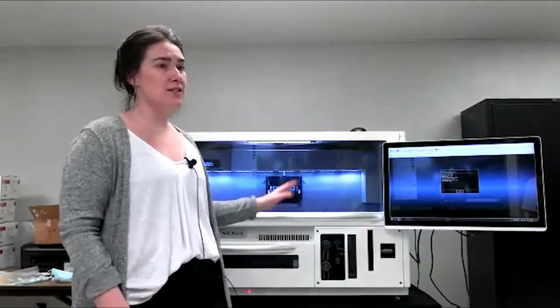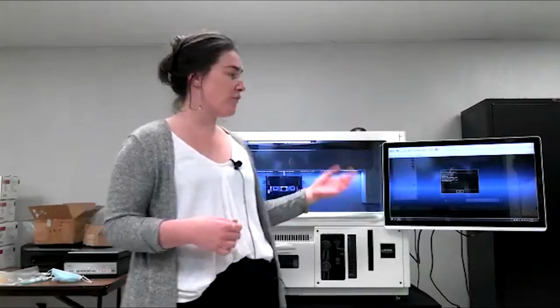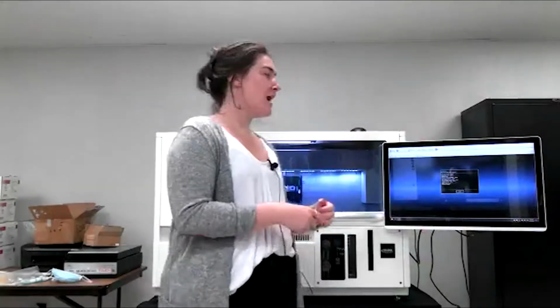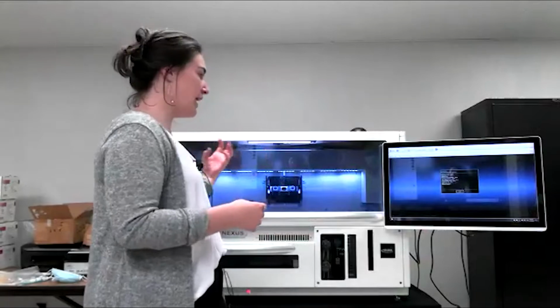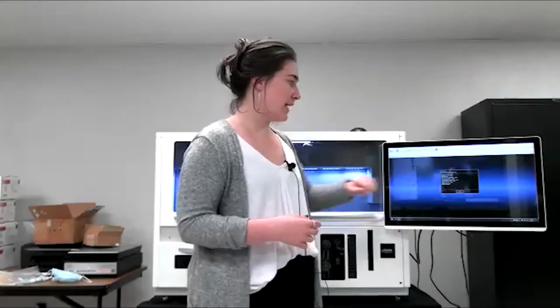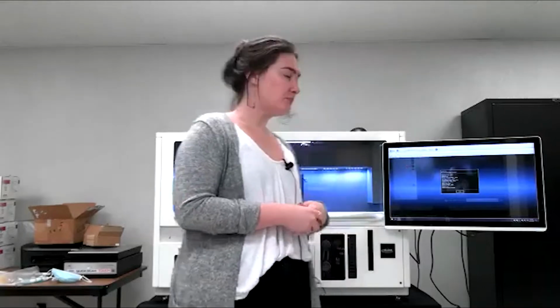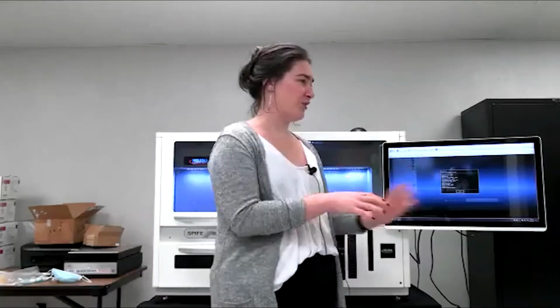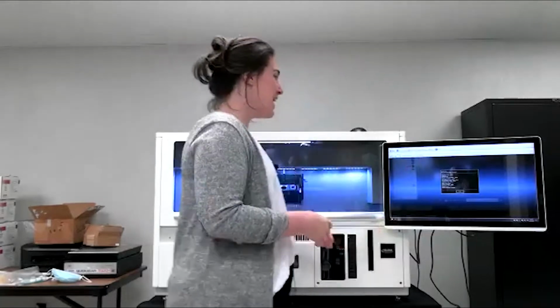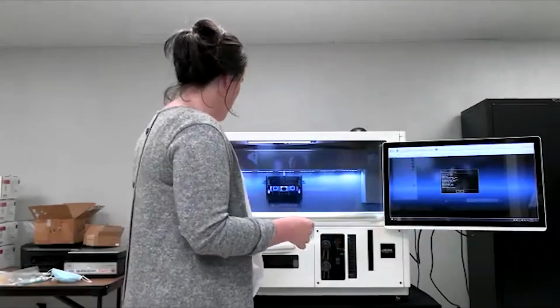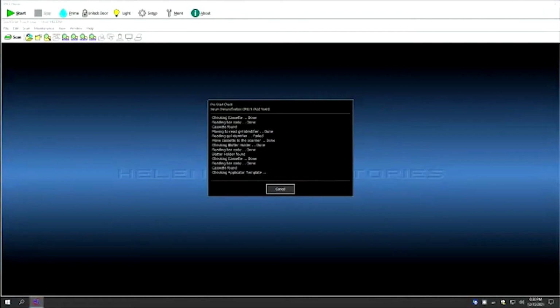And the SPIFE Nexus begins checking to make sure I have each piece in place. If I had not had my dryer cover in place, I would have gotten a warning. It's checking for my cassette now. It'll go to each individual place, make sure all my components are where they should be to begin a test, and then it'll start the run. I'll stop it at that point so you don't have to sit here and watch an entire run. But it goes through the entire checking process. And then it'll begin the run.